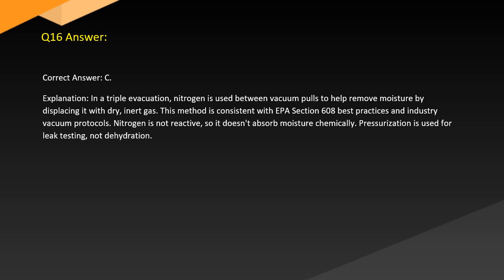Answer. Correct answer: C. In a triple evacuation, nitrogen is used between vacuum pulls to help remove moisture by displacing it with dry, inert gas. This method is consistent with EPA Section 608 best practices and industry vacuum protocols. Nitrogen is not reactive, so it doesn't absorb moisture chemically. Pressurization is used for leak testing, not dehydration.